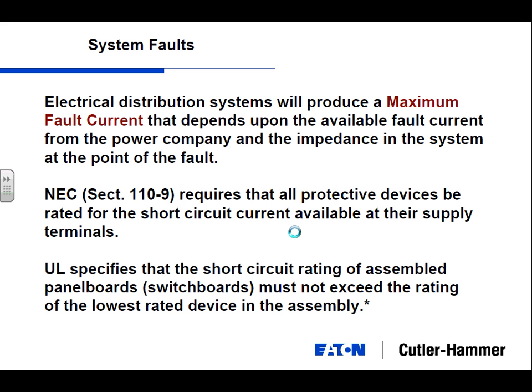UL then takes what NEC requires and translates it: the short circuit rating of the assembled panelboards or switchboards must not exceed the rating of the lowest device in the assembly. And I'm going to put an asterisk on there that we'll circle back to. So if I've got an assembly of a panelboard and I've got 10,000 amps available fault current, the least rated device in that panelboard has to carry that 10,000 amp rating.